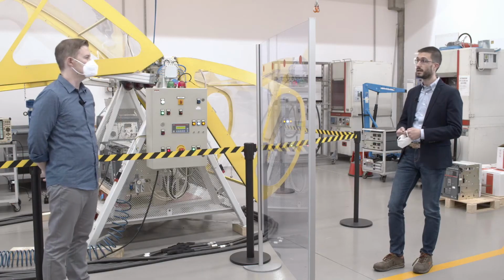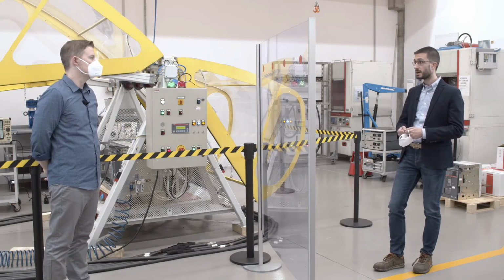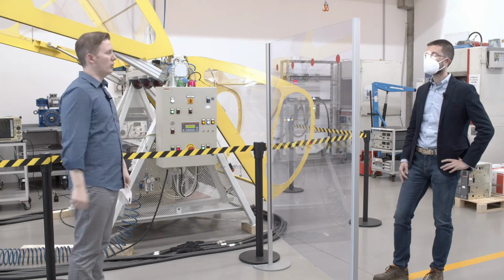But maybe it's advertisement, I don't know. But also they are working with a lower time constant, not typically 15, 20 milliseconds like is possible in our lab. Moreover, we try to break a bit the common boundaries of low voltage DC applications. We have the chance to test here in our lab up to 2000 volts DC, even if delivering lower current. And again, in Asia, there are some other labs that in the near future will arrive at 2000 volts. Thank you, Davide, for your contribution.